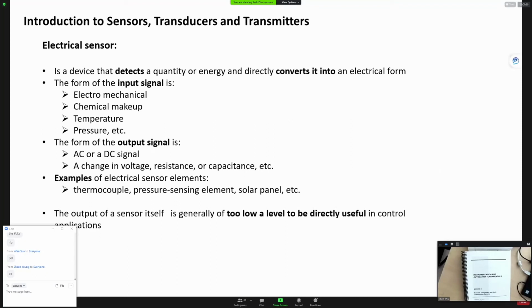A PLC is usually taken as a controller. So you will take the sensor's output and go through an amplifier. If you have a simple control, you might have a simple controller. If it's a very complex control, then you will put those inputs through a certain type of amplifier, then convert them into PLC inputs.